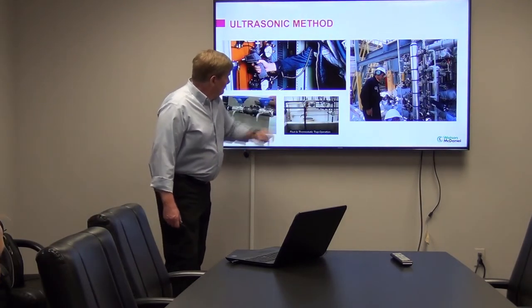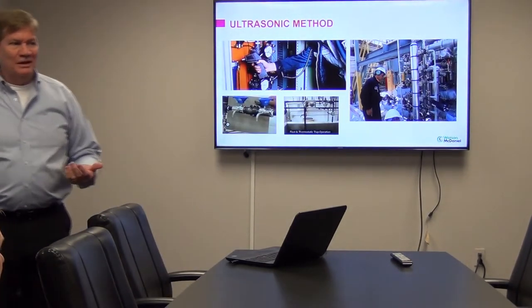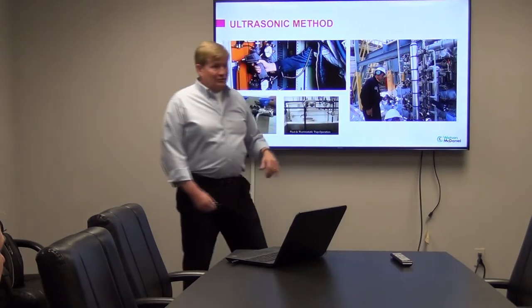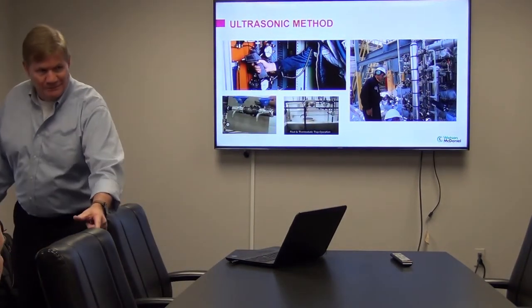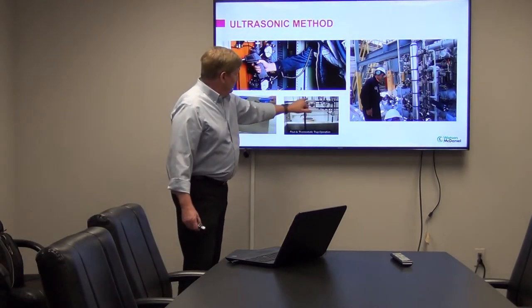These guys, we'll see in the video in a second, that's a float and thermostatic trap. It's a constant modulation. And years ago when I used to go out with testers with the guys from Spirax Sarco, they'd go up to a float and thermostatic trap, put the little probe on, good, bad. And I challenge them, tell me that trap is good or bad. You have to have an understanding of what's actually happening in the trap.